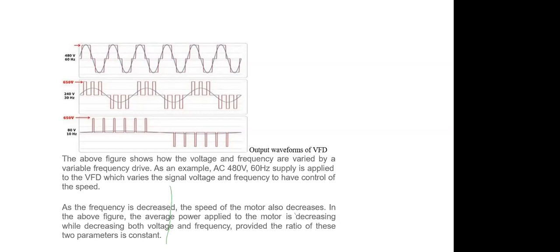So at any point of time, when we say the motor is running at 1000 RPM, that means we have converted it to DC, and the width of this pulse is reduced proportionally, and that is again applied. Now, again, it's an AC motor. The DC cannot be applied to AC for running purpose.